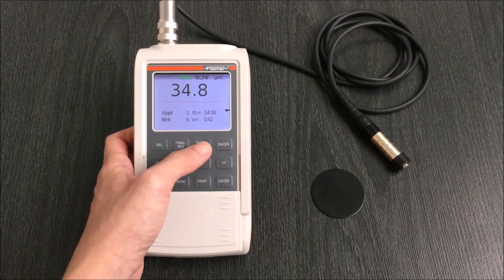Finally, block results and final results can be viewed on the FMP instrument. Press block results to show the block results which includes statistical information about each block. Press final results to show the overall results including a histogram.